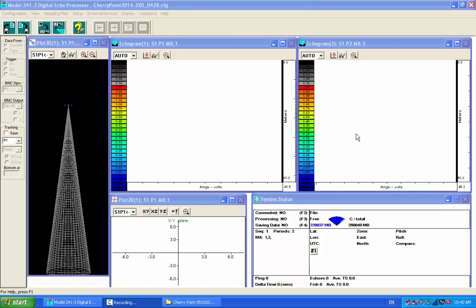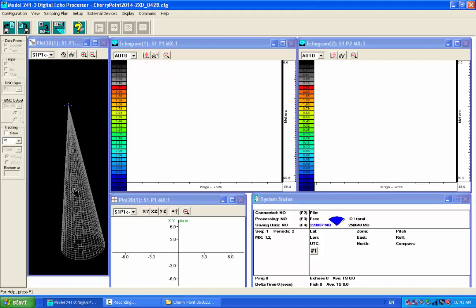your side-looking transducer. And you can set up your displays to either be target strength corrected, showing the target strength of your individual fish, or the voltage, the uncorrected amplitude. And most folks will do the target strength corrected. This is actually from that herring survey I just finished. I brought it up as an example, and it has a little more pixelation and resolution on the voltage data. And again, the display screen doesn't really affect your data at all. It's just really how you want to look at it.